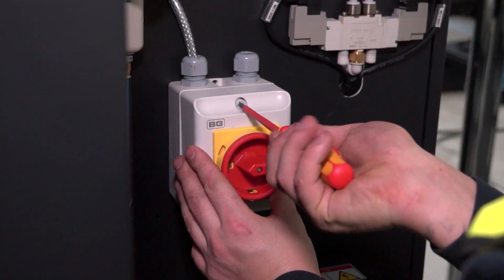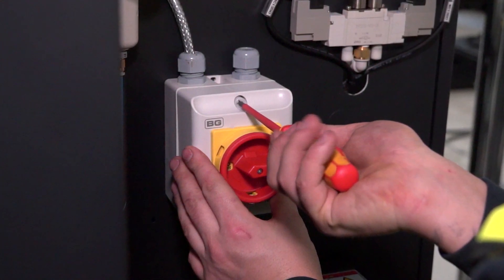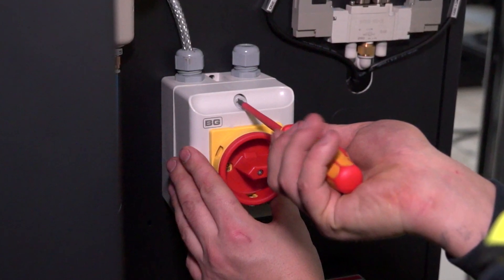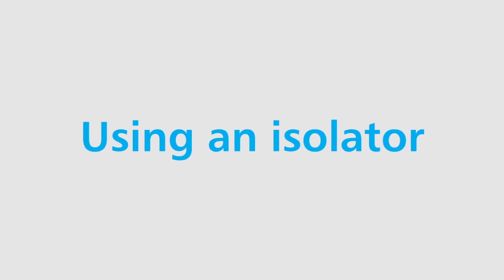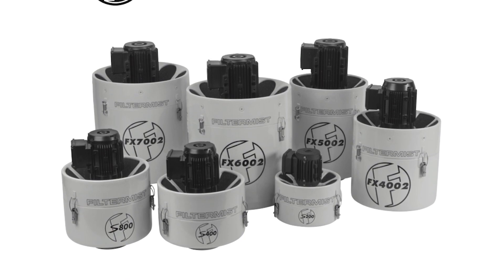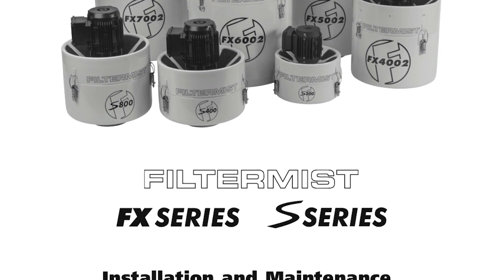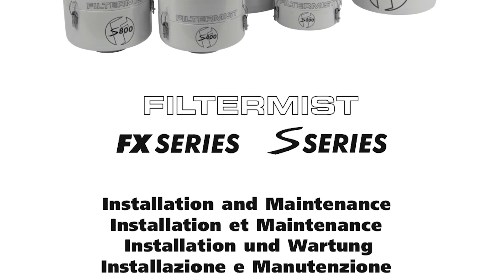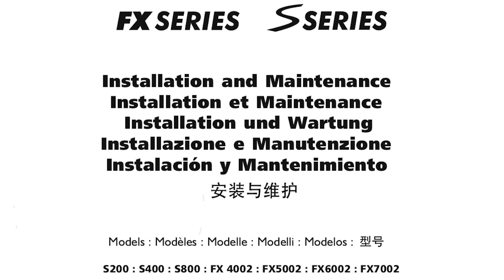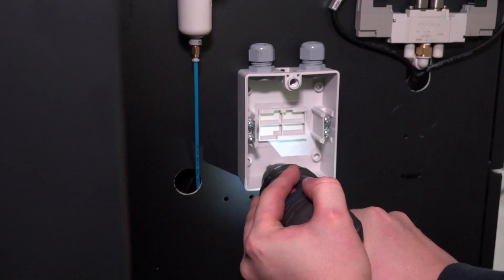Connect via a direct on-line starter and isolator with suitable thermal overloads, or via an independent supply in the machine control panel. Using an isolator allows the Filtermist unit to be classed as a machine according to the Machinery Directive 2006/42/EC. Please refer to the installation manual for recommended overload settings and terminal connections. Fit the isolator onto the machine tool.